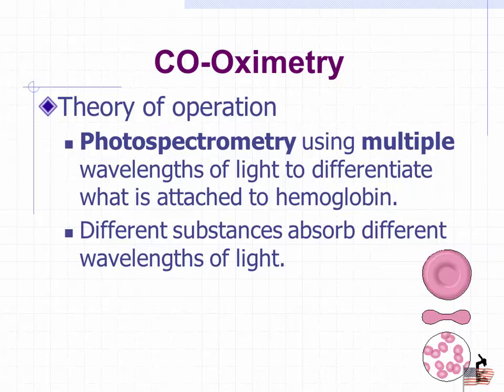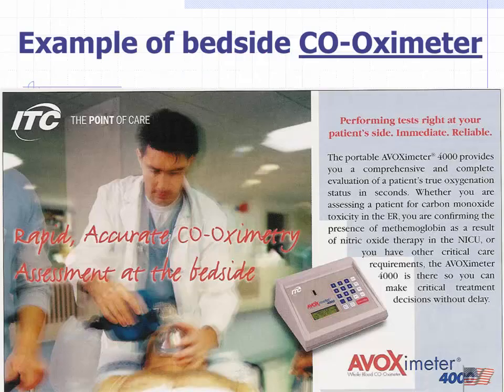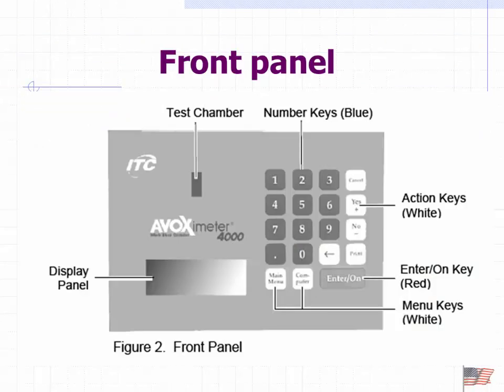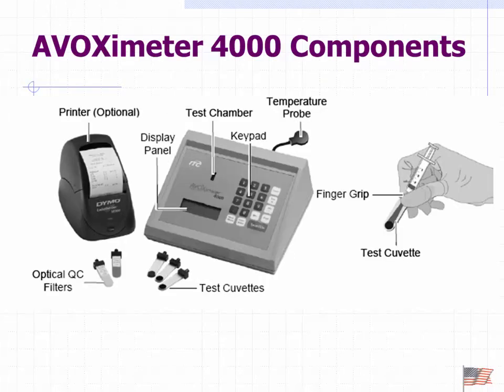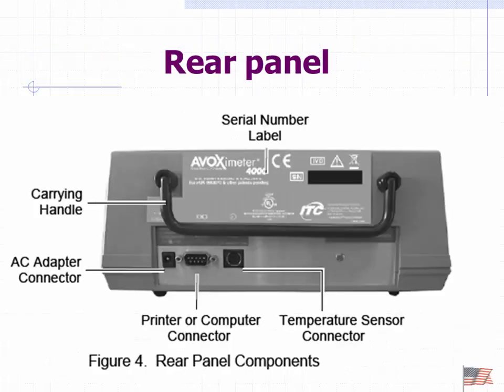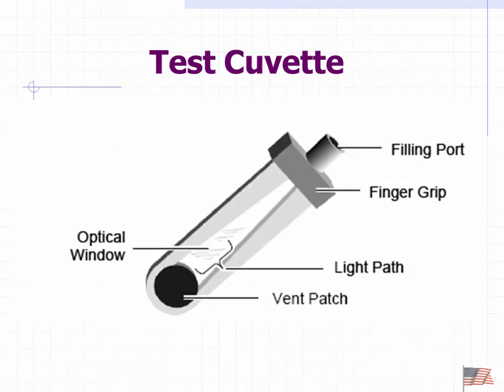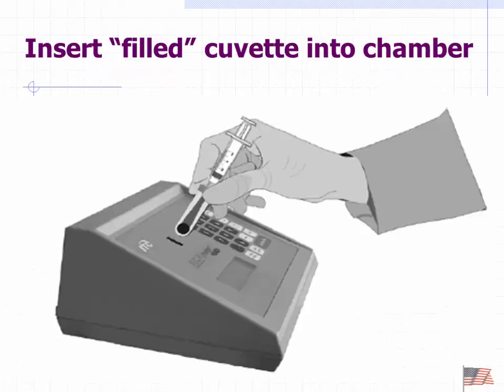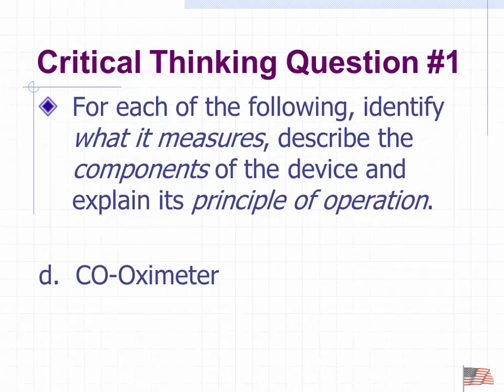Just briefly want to talk about CO oximetry, using again that photospectrometer method to scatter light to be able to measure the different species. There is a bedside CO oximeter. I'll just make mention of it, and we'll be done with it. How's that? Okay. This is what the panel looks like. There's a little test chamber that we're going to put a little cuvette into. Here you can see the test cuvette. We're going to go ahead and fill it with blood, place it in there, and just like the CO oximeter, it'll go ahead and run various wavelengths of light. Again, it is a portable bedside, just like the IRMA is. And you can see our little optical window there where the light shines through and the blood collection port. And put it in the machine, and we don't need to worry about that one.